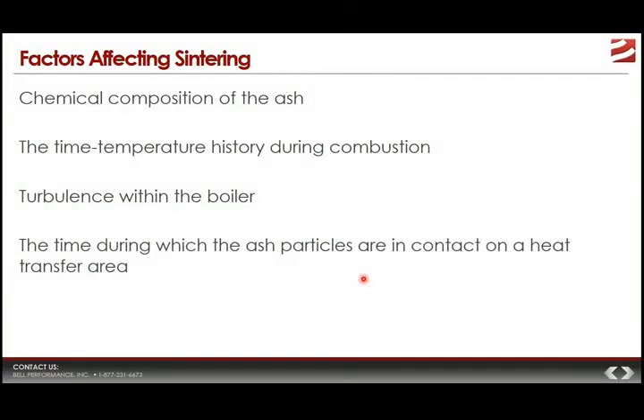The factors affecting the sintering process include: first, the chemical composition of the ash, which relates to the chemical composition of the fuel oil itself — vanadium and sodium levels and the ratio of other inorganics; second, what they call time-temperature history; third, turbulence within the boiler and how airflow moves within the combustion area; and fourth, how long ash particles are in contact on a heat transfer surface.